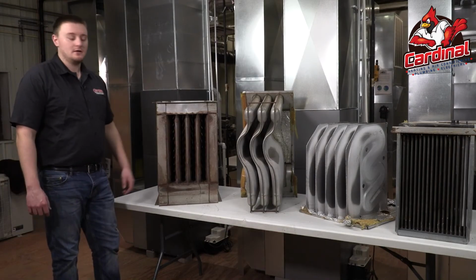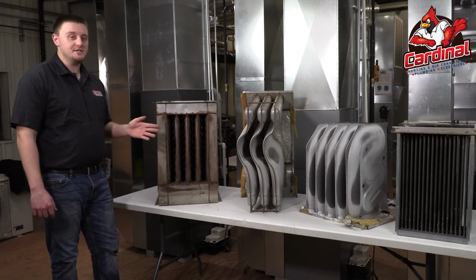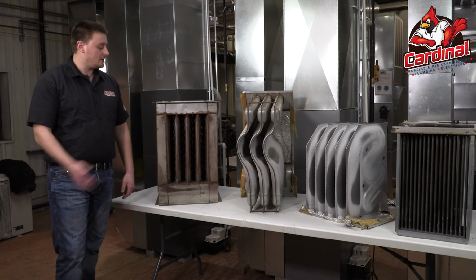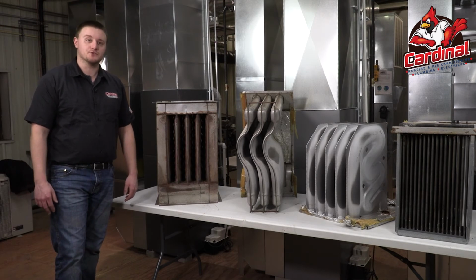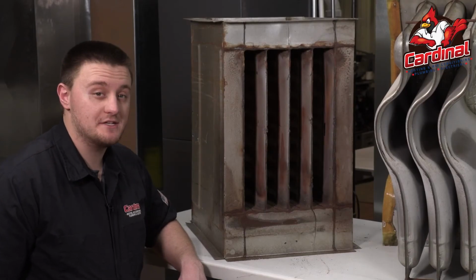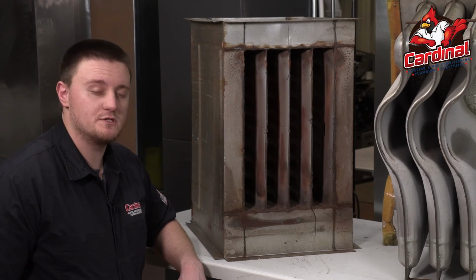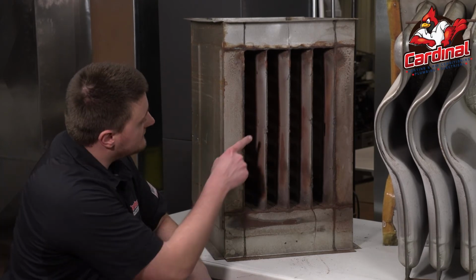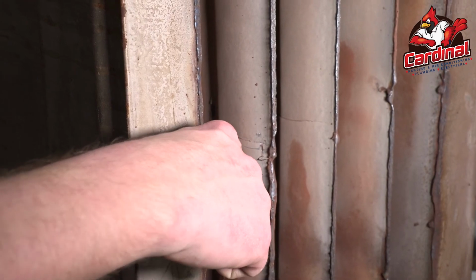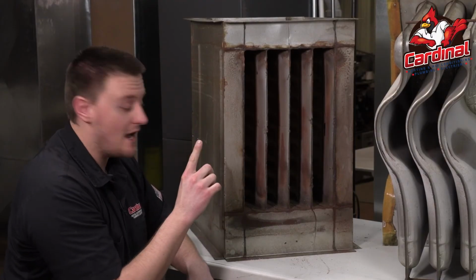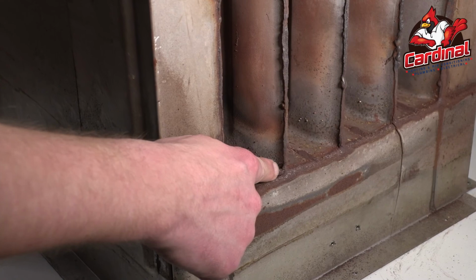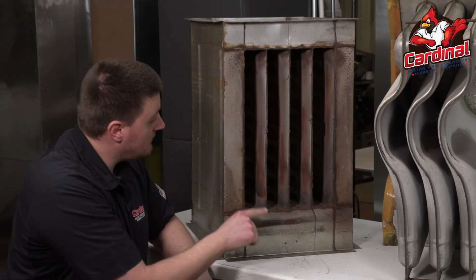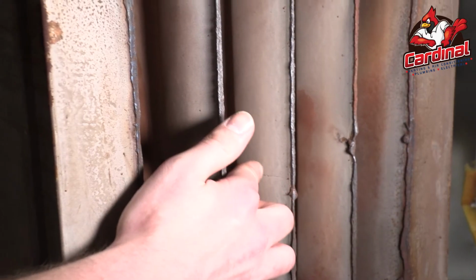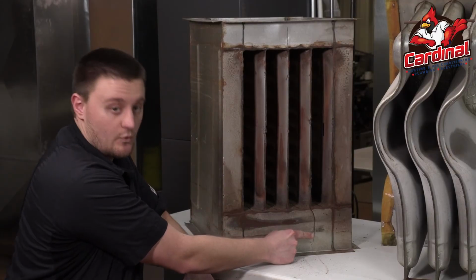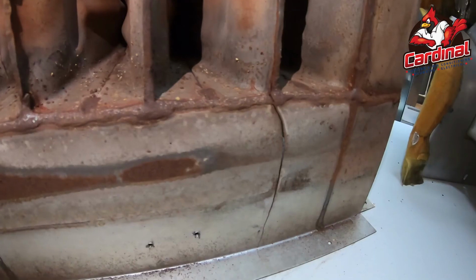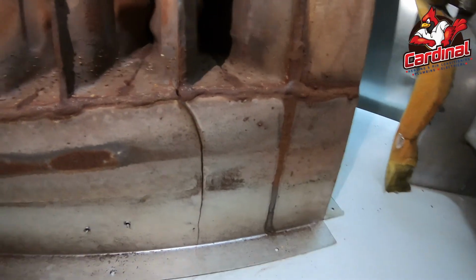So over in this area, we have a few different examples of different heat exchangers that have failed. We're going to get a closer look so you can see what the failures look like. So this heat exchanger has seen better days. The most noticeable crack that we can find is going to be this one right here in this first cell. There's actually another crack on the same cell right here at the bottom. We go over to the next cell, we have another big crack right here in the middle. You can actually see this one very visibly down here as it comes to the bottom of this cell.